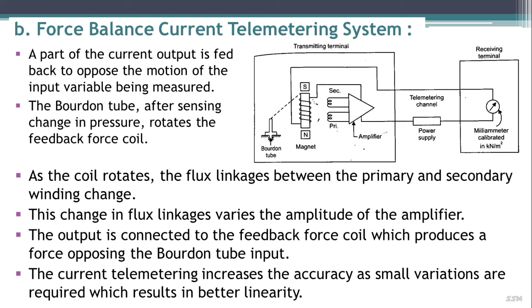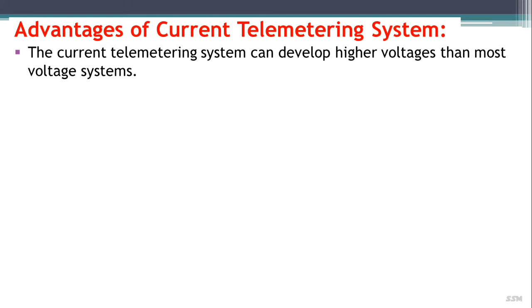Next we'll discuss the advantages of the current telemetry system. The current telemetry system can be developed at higher voltages than most voltage systems, and consequently it can be made more immune to the effect of thermal and inductance voltages in the interconnecting leads as well as line resistance. A simple DC milliammeter can be used with special calibration for line resistance. Several receivers can be operated simultaneously. The receiver signals can be added or subtracted directly. Changes in the line resistance are compensated by the basic feedback method. The response of the system to an input change is almost instantaneous. The energy level is adequately high to minimize the effect of extraneous voltages.